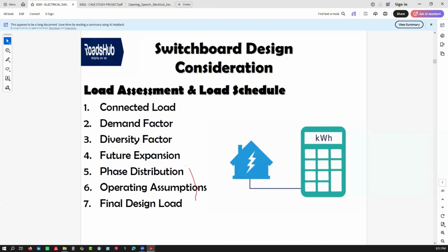Future expansion - if you really want people to benefit from what you give, you need to design your system so that if they add any load, the system will sustain whatever output it needs. Phase distribution - you don't want to imbalance your phases. You have red, yellow, blue. Make sure the current flowing through those cables can balance. Doing that, you assign a load schedule that will distribute the loads efficiently.